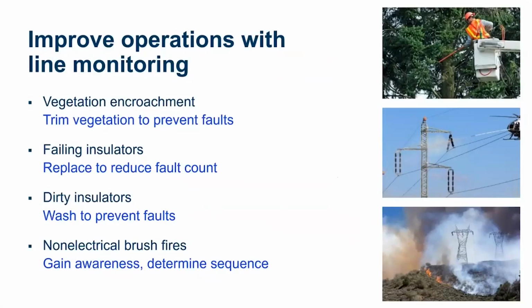Last thing is we might be able to gain awareness of where fires are. So maybe this line didn't cause a fire, but there is a fire in the area. Hoping that with all the smoke rising up and all the ash in the air, we're going to see these traveling waves launch. They're non-trip traveling waves again. They're just traveling wave events, and we can gain awareness of where these wildfires are.